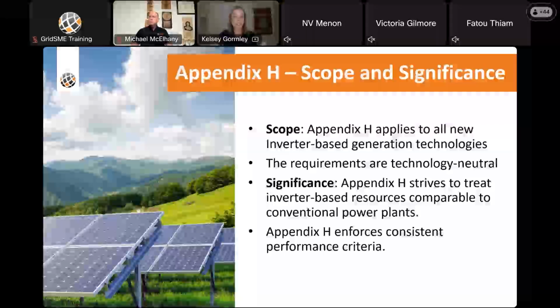So in terms of the scope, Appendix H applies to all inverter-based generating facilities connecting to the CAISO grid. That means large-scale solar farms, wind plants, standalone batteries, hybrid solar and storage projects, they all fall under these rules. So if you're bringing on a new PV or BESS project into the CAISO, you will be required to comply with Appendix H. It is technology neutral. It doesn't matter if it's PV or storage. The performance expectations are very comparable for all the fuel types that I just listed. So the idea is to treat inverter-based resources as first-class generating units that are subject to reliability standards similar to other conventional generators, but tailored to the specific power electronics nature of these resources. So this way, as California's grid becomes increasingly dominated by and reliant upon these inverter-based resources, we maintain that consistent reliability baseline.